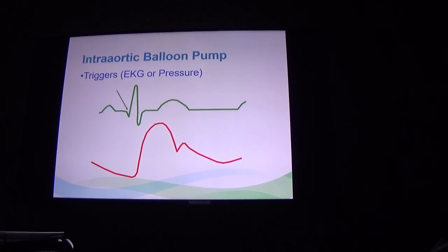Again, the balloon pump will operate on its own, and even during arrest, asystole, VFib, VTach, whatever, the balloon pump will still work just fine. And it will work just fine even if you're in asystole and you're doing compressions, because if it's in auto mode, instead of triggering off the EKG, it'll trigger off your compressions. So if you show up on the floor and someone's in arrest with one of these devices, and they're freaking out asking you what to do with them, just leave it in auto. It's going to be just fine.